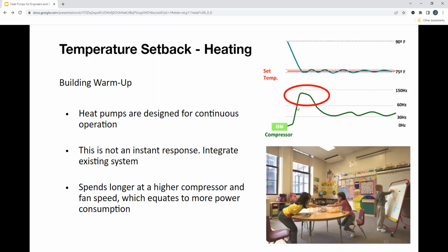And by doing an 8-degree, 10-degree setback for building warm-up purposes, this is going to draw a lot more energy, and it doesn't really make sense from a VRF operational standpoint when you're running that. So I know a couple contractors that have spoken to this. They said, hey, I left the set point on, same set point it runs throughout the day, throughout the night, and there was an incredible amount of energy savings associated with that versus going back to their old ways and starting building warm-up an hour and a half, an hour before when school is about to start, when the doors open. And the compressor speed and amount of time definitely depends on the building and the weatherization of that building.